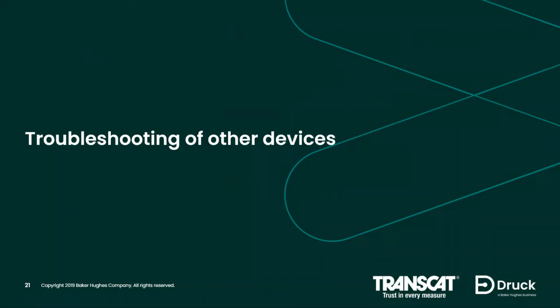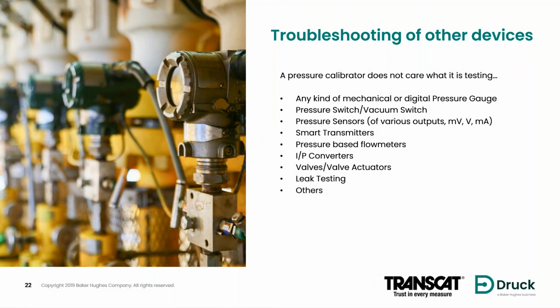So just a brief word about other devices. A pressure calibrator doesn't really care what it's checking. It's agnostic. So any kind of mechanical or digital pressure gauge, pressure switch, vacuum switch, pressure sensor. We talk primarily about 4 to 20 milliamp devices, probably the most common, obviously, but there is the capability for low-level output, millivolt level output devices, as well as amplified voltage.